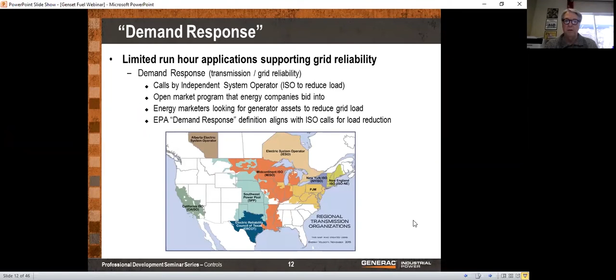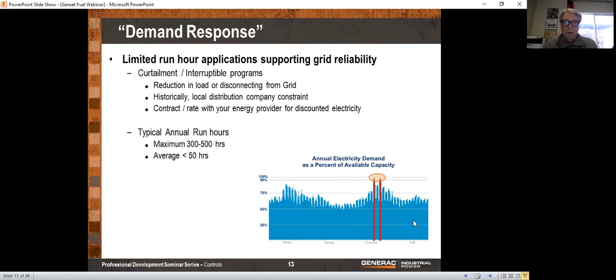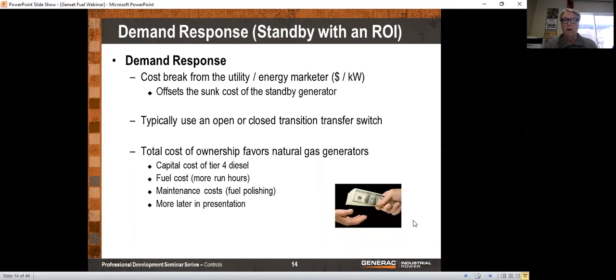Generally there are limited run hours. The utility will say they won't run your generator more than 300 to 500 hours, but actual experience is less than 50 hours. I have a lot of experience with this because I was director of engineering at a steel plant with a 50 megawatt generator doing exactly this - the utility used us whenever power was short to provide excess power. On average, I didn't see more than about 4 hours a year. So that's typical: you get a standby generator that runs very limited time, and you get a decent break on your electric bill.